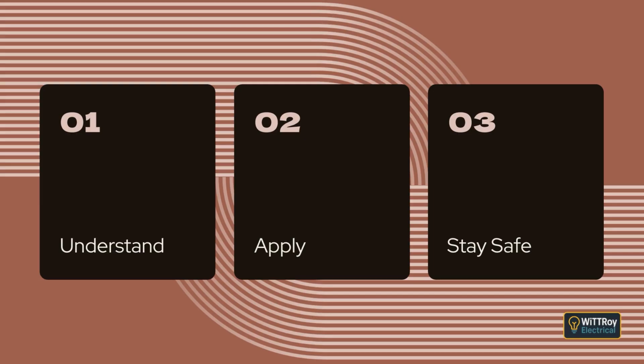Under the New Zealand Building Code, building insulation is required. Where building insulation is already fitted and recessed luminaires are retrofitted, added, or altered, precautions must be taken by the installer not to compromise the safety of the installation. Clause 4.5.2.4, Suspended ceilings. Luminaires that are supported by a ceiling panel shall not present a mechanical loading that exceeds the capacity of the ceiling panel, and shall not operate at a temperature that would cause deformation, discoloration, or other deterioration of the ceiling panel.